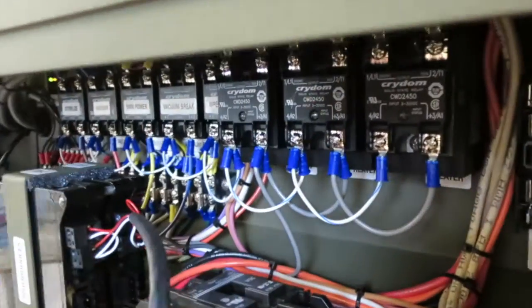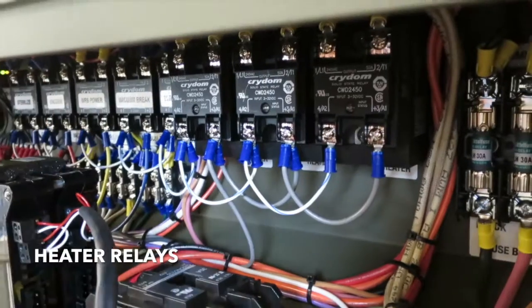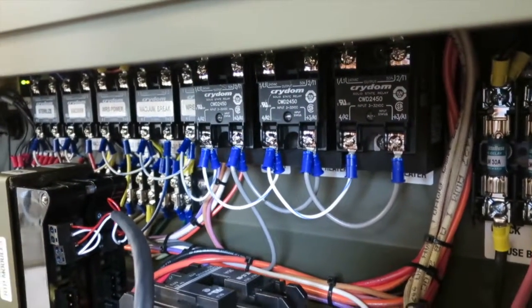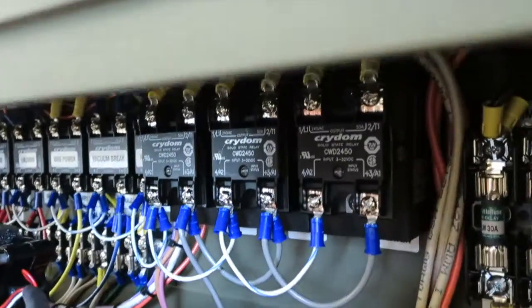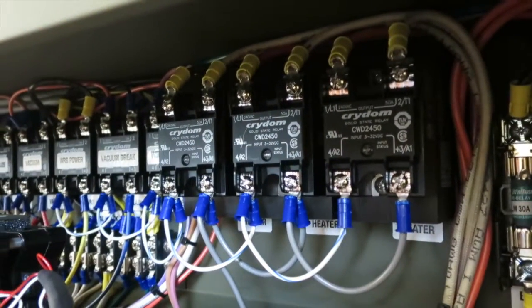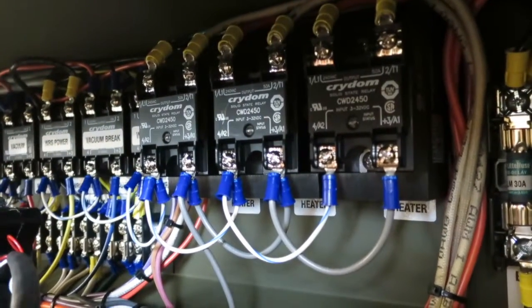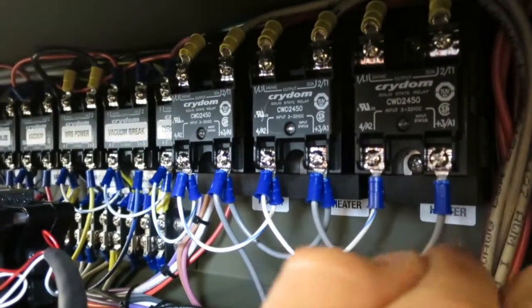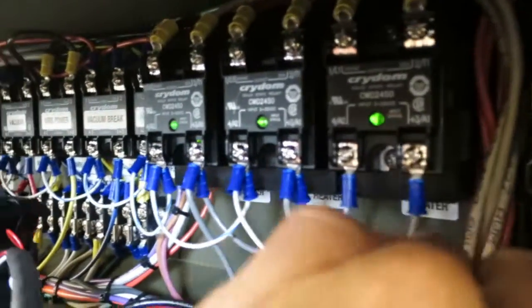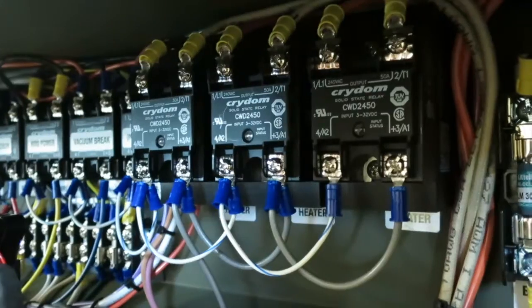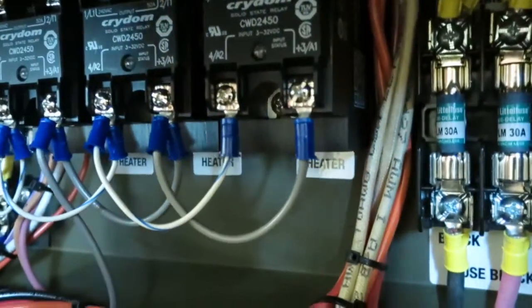Right here, these 3 relays, very important relays here. We got 3 because each one corresponds to a heater element. Remember I was talking about the heater element wires down here. Those connect to the top of those 3 relays. And you can see those LEDs that were just blinking. Those are blinking because every time the PLC says to turn on the heater elements, it's supplying 24 volts across the bottom through this gray wire. And it's firing those relays, which is connecting the circuit across the top and allowing power to flow down to the heater elements. You'll notice they're mounted on pretty big heat sinks. That's to keep them cool during operation because they're firing very often, and that allows them to stay cool and not overheat.